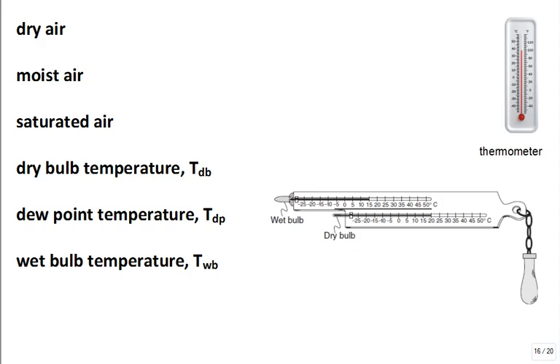And if that cold surface of a can is below the dew point, you're going to get condensation on that can. If the window surface temperature is lower than the dew point of the air in the room, you're going to get condensation on that window. If you have a big room or outdoor air in its temperature, dry bulb is known, temperature, dew point is known. And somehow you cool it by radiative cooling overnight. That's how things cool off at night. There's no sun, clear sky, it radiates out, and we cool off. If the temperature of the dry bulb drops to the dew point and then tries to drop more because it's cooling, you will get dew. Dew forming on the grass, dew forming on the cars. There's one other temperature that we need to be exposed to. It's the wet bulb temperature. How many temperatures do we have now? Three temperatures. Dry bulb, easy. Dew point, I've got to think about it, but I have a lot of experience.